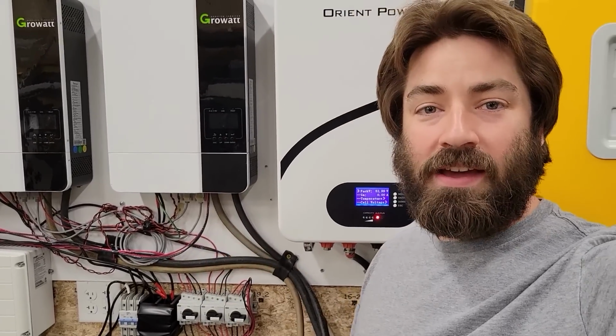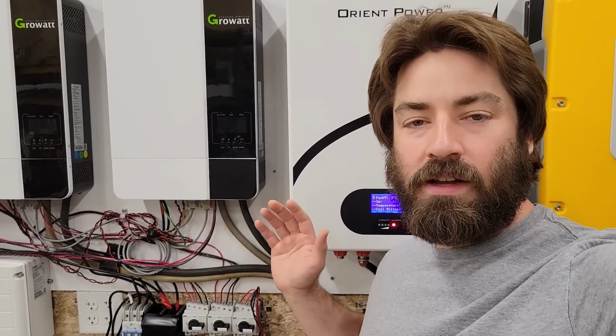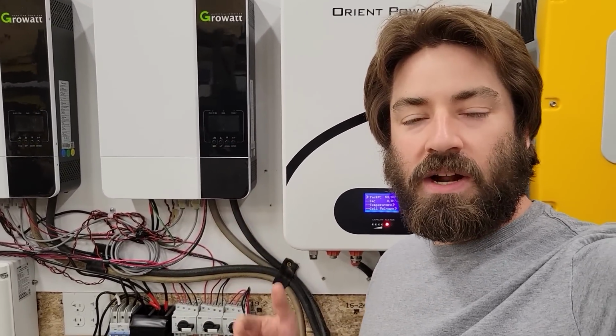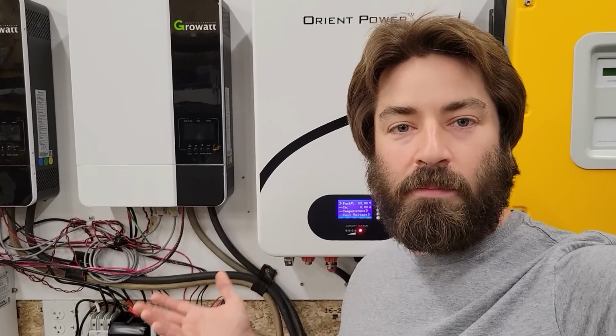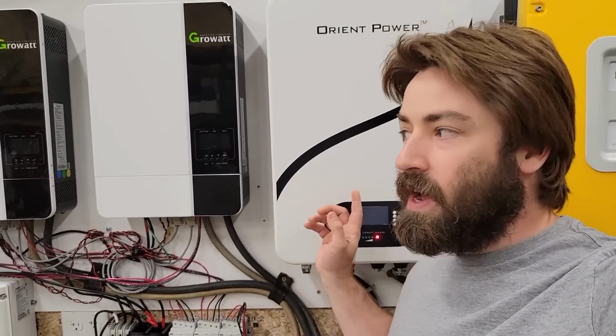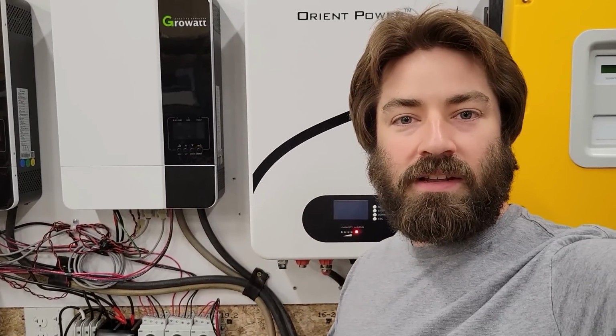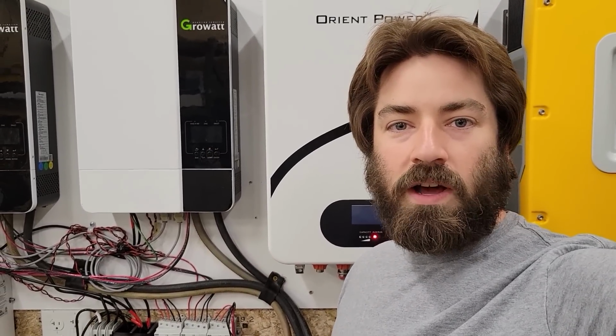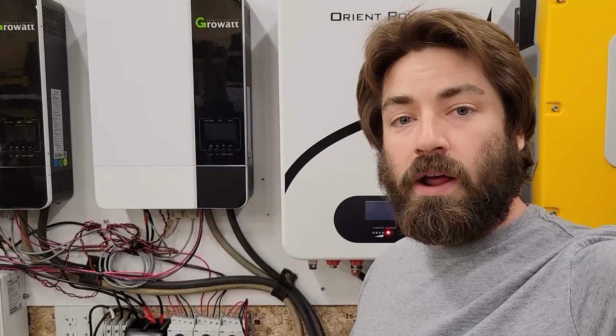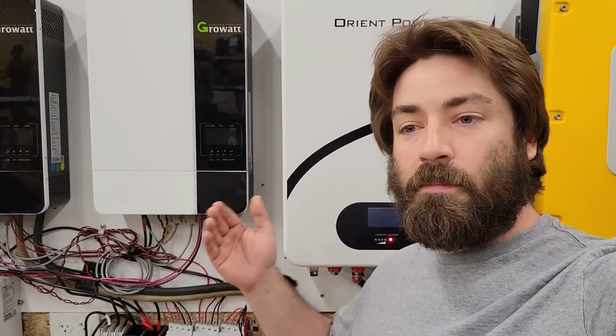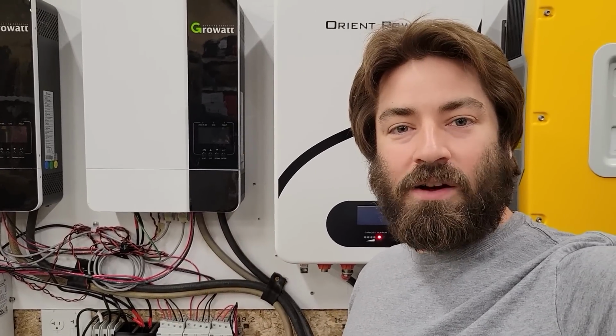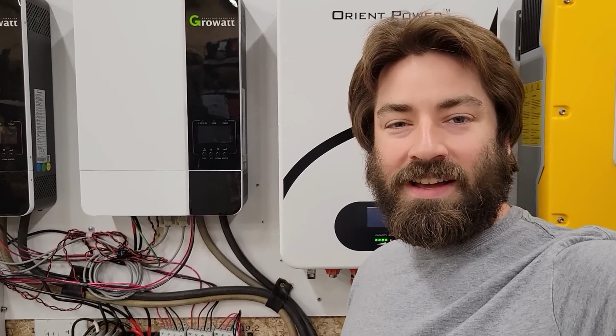But that's okay, it's part of the deal, we're just finding its limitation. I wanted to see if it had any surge ability, and it doesn't look like it does. So if you're going to buy this battery, keep in mind it's limited to 100 amps. It probably can do 100 amps fine though, which is what we're about to test. We're going to run 100 amps for an hour and see if it works.